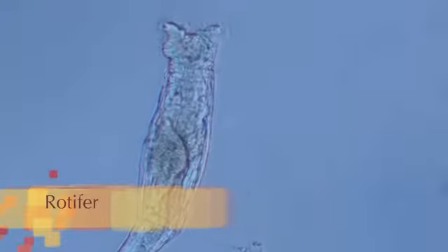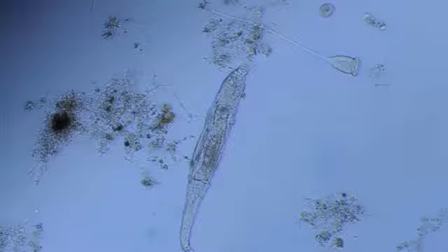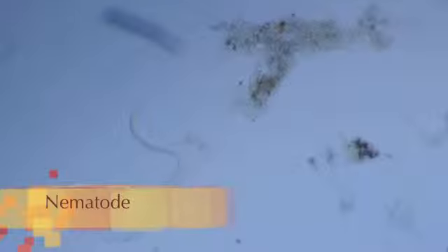And rotifers. These are a higher life form with cool hairy mouths and are much larger than many of the other bugs we see here. Some forms are much more mobile and move around constantly. Others, a little bit less active. Now our worm friends, the nematodes. These tiny worms, who can be active or just swimming lazily around the neighborhood, can also be an indicator of certain conditions. Both nematodes and rotifers can be indicative of an older bacterial biomass and in wastewater are indicative of a higher degree of purification or seeding from an attached growth system.